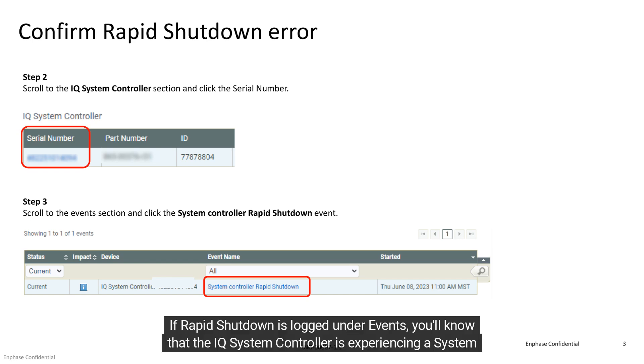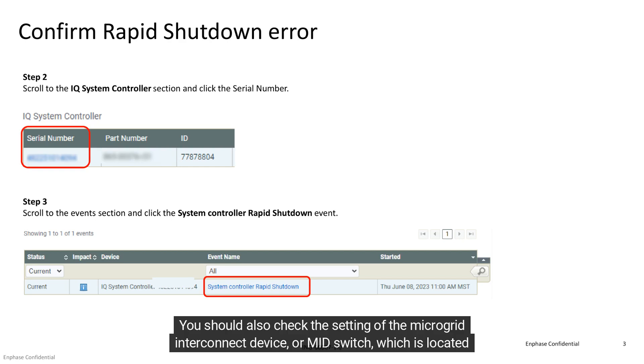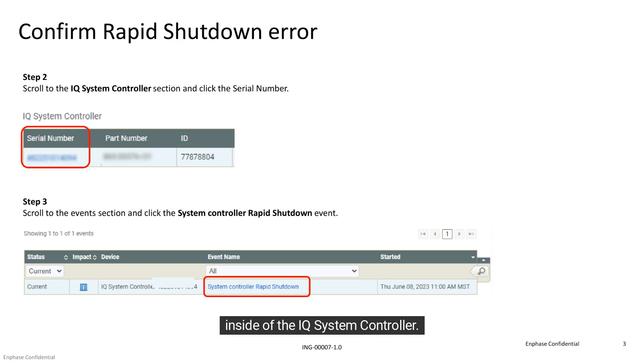If rapid shutdown is logged under events, you'll know that the IQ System Controller is experiencing a system shutdown error. You should also check the setting of the microgrid interconnect device, or MID switch, which is located inside of the IQ System Controller.